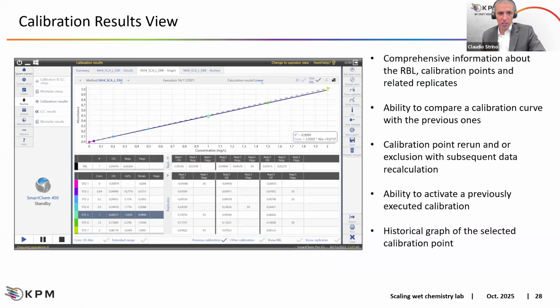Calibration results view. This is really appreciated by a lot of customers because it's very comprehensive. We have all the information we need concerning the reagent baseline and the calibration curve. We can see everything is coded by color. Each color in the grid matches the color we have in the screen. We can review at any time the reaction of each point or compare the reaction of all the replicates in the same graph. And moreover, we can also compare the current calibration, the blue line, with any previous calibration we have in the archive. Moreover, we can open the archive and select and set as active any previous calibration. Moreover, when selecting a single calibration point through the show history feature, we can see the trend over time for the point of interest.